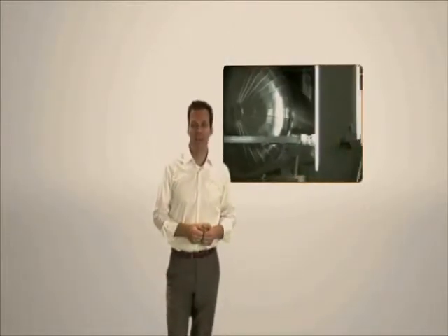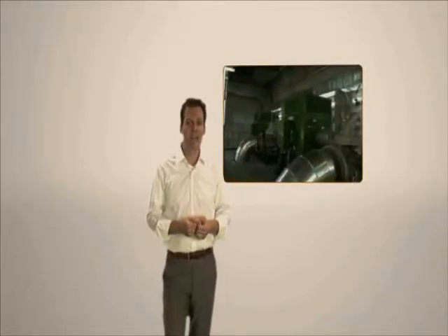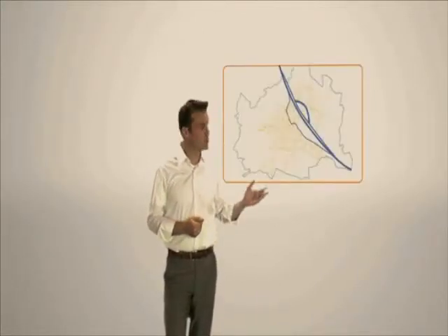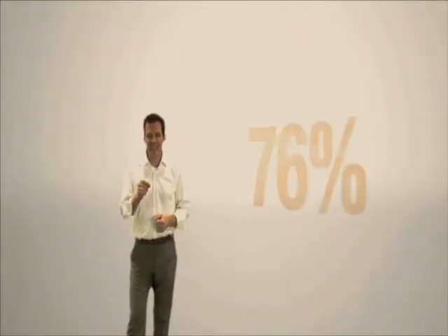The steam taken from the turbine is used for the generation of district heat. It condenses to water in a heat exchanger and delivers its heat energy to the district heating network of the city of Vienna. This energy covers the heat demand of 50,000 homes. By using the heat energy that develops due to the thermal handling of the waste, the degree of efficiency is 76%. Parallel to the extraction of energy, the fight with the flue gases starts now.